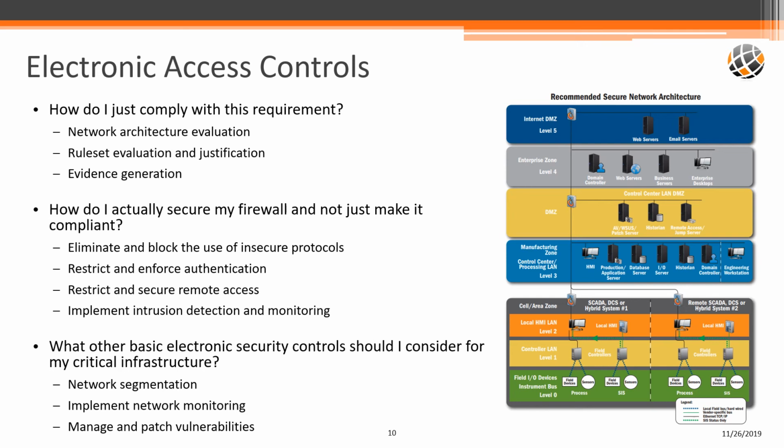We saw there was an event in March where, due to unpatched Cisco ASA firewalls at 12 different low impact facilities and a control center, they were continuously rebooted due to a very easy to exploit vulnerability that already had a patch out there from Cisco. So that was a near miss event that could be easily avoidable by just having a strong vulnerability and patch management program in place.